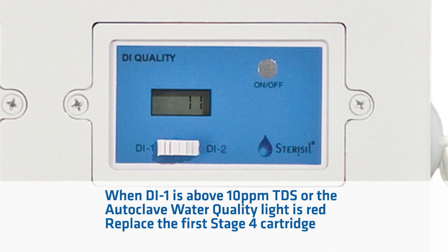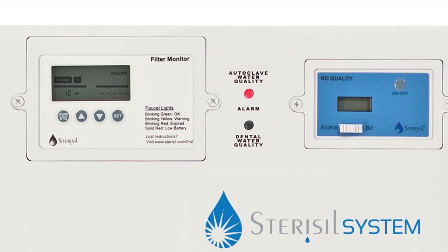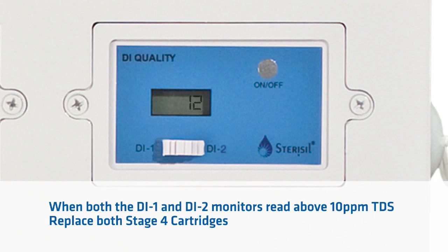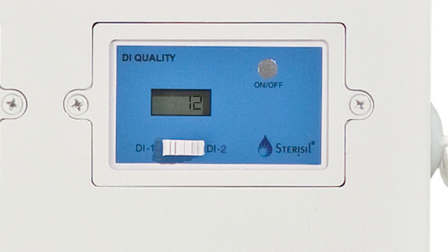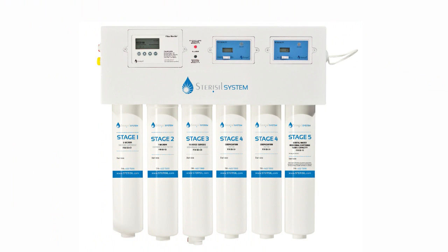When the DI1 monitor reads above 10 parts per million TDS, representing the condition of the first stage 4 cartridge, or the Sterisil system's autoclave water quality light on the faceplate of the system is solid red, replace the first of the 2 stage 4 cartridges. When the DI1 and DI2 monitors read above 10 parts per million TDS, replace both of the stage 4 cartridges. To maximize the life of your stage 4 cartridges, remove and dispose of the first stage 4 cartridge and rotate the second stage 4 cartridge into the first stage 4 cartridge position. Insert the new stage 4 cartridge into the second stage 4 position.